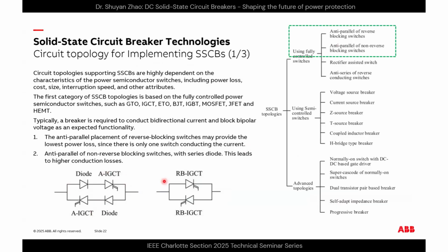The first category of topology is based on full controlled power semiconductor devices such as GTO, IGCT, ETO, BJT, IGBT, MOSFET, JFET, and HEMT, which is a GAN device. Typically a breaker is required to conduct bidirectional currents and block bipolar voltages, because in DC systems we more often see energy storage that needs bidirectionality. The anti-parallel placement of reverse blocking switches may provide the lowest loss, since there is only one switch conducting the current, whether current flows left to right or right to left.